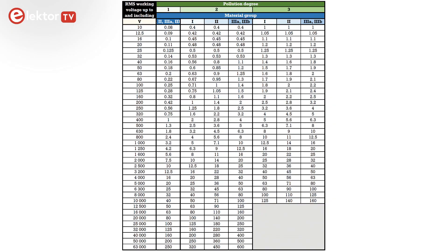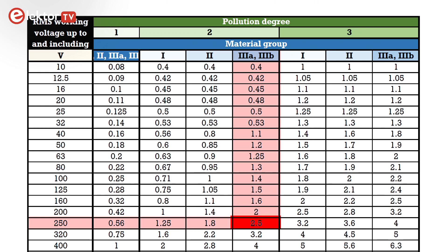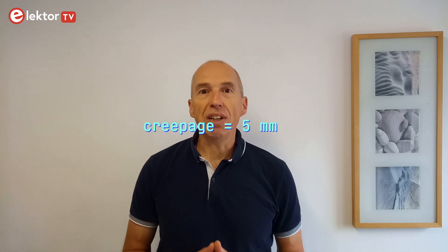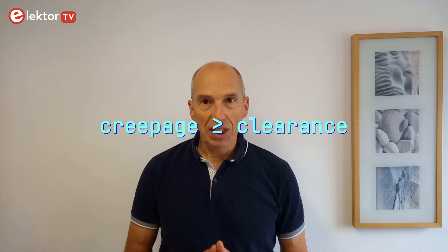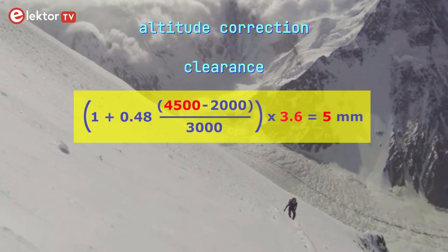In my draft standard the creepage distance between the primary and secondary circuits is obtained from Table 17. We find 2.5 mm, but this is for basic and supplementary insulation only. Since reinforced insulation comprises both, this value must be doubled and we get 5 mm. Note that this value also works for materials in the 3B group. The creepage distance is always larger than or equal to the clearance distance. If you stick to 5 mm for creepage, then the clearance distance will be 5 mm too instead of 3.6 mm, and you are good for altitudes up to 4500 meters.